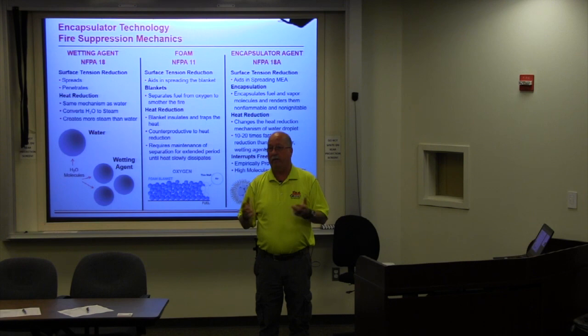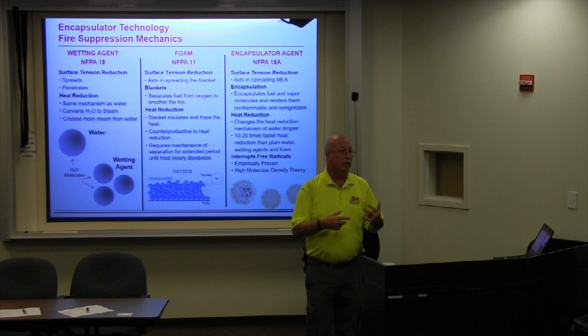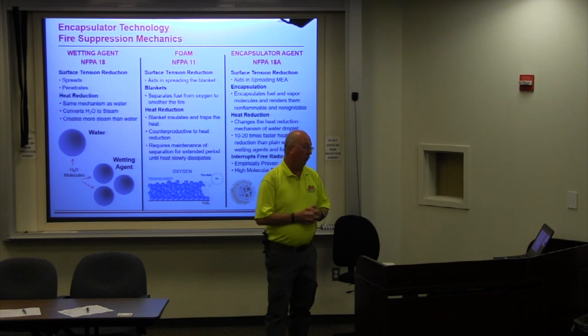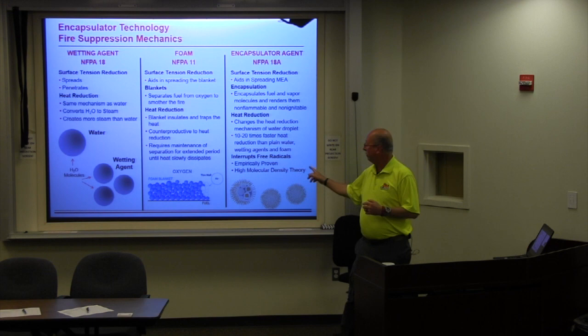There's nothing that you have to fall under that makes you a Class A foam. When you start going into the Class B foams, you do have test standards. You have your burn back resistance and different criteria that have to be met in order to fall under that Class B foam standard. And the same is going to be true with encapsulator technology. Section 7.6 that I showed earlier is that standard.